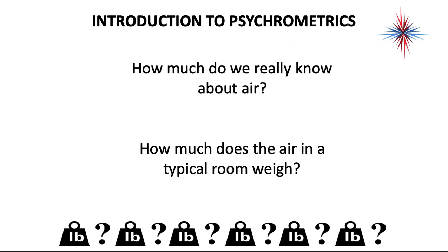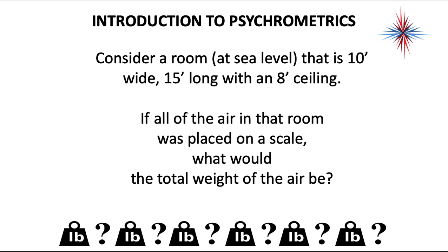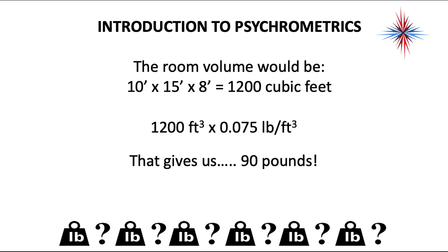What do we really know about air? How much does the air in a particular room weigh? Consider a room at sea level that is 10 feet wide, 15 feet long, with an 8-foot ceiling. If all of the air in that room was placed on a scale, what would the total weight be? We have to move air to cool and heat buildings, so the room volume is the first thing we calculate: 10 by 15 by 8 equals 1,200 cubic feet. 1,200 cubic feet times 0.075 pounds per cubic foot gives us 90 pounds. One cubic foot of air is 0.075 pounds.